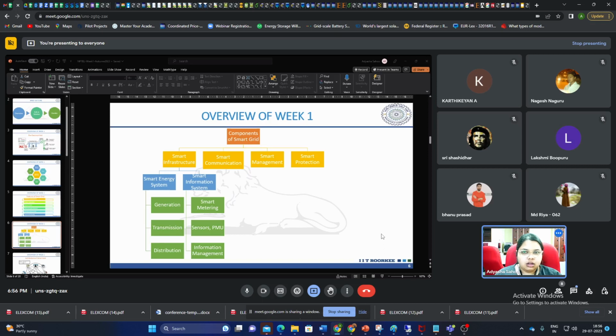As I said earlier, these relays and circuit breakers were all habituated to the former practice of unidirectional power flow. When DERs, distributed energy resources, come into the distribution system and inject power back to the grid, sometimes even if it is not a fault condition, since they are not habituated to these practices, the relay setting may not work. So again, we are revisiting this practice of protection.